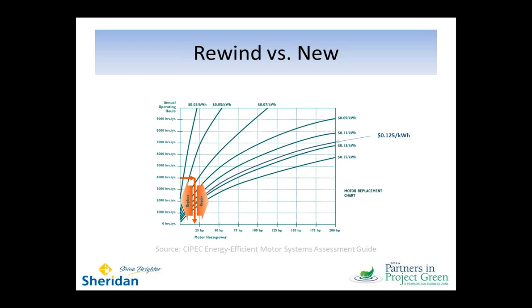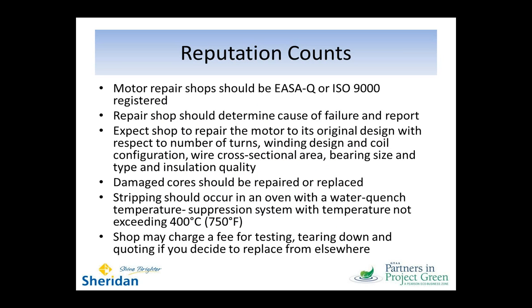Standard efficiency motors should probably not be rewound if you find that the cost to repair that thing is going to be more than about 60% of the cost of a new PEM, because at that point the economics work in favor of replacing it. And a note on that, if you're going to send something out to rewind, not all shops are created equal. So I keep going back to this theme of not all things are created equal. And certainly in repair shops, you've got to do your homework with these. And in your planning, you should think about having a vendor or two selected to do your rewind work.